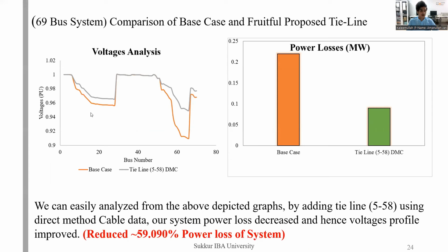Here we can clearly see that with reference to the base case, by connecting a tie line from 5 to 58 using the direct method cable, the voltage profile is improved. And the power losses reduce from 0.21 megawatt to 0.09 megawatt. So we can easily analyze from the above depicted graphs that by adding a tie line from 5 to 58 using the direct method cable data, our system power losses decrease and hence the voltage profile improves. So here we have reduced almost 60% of the power losses of the system.